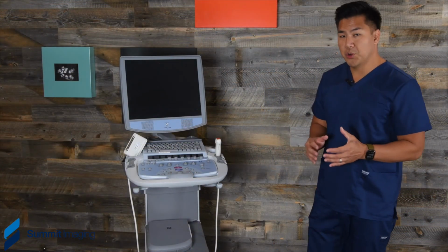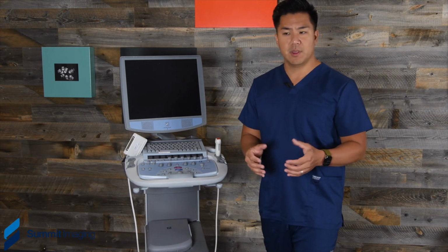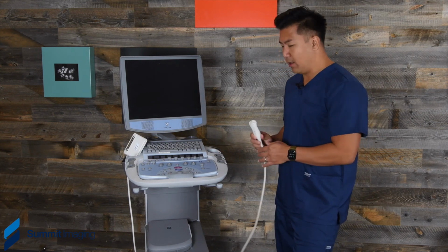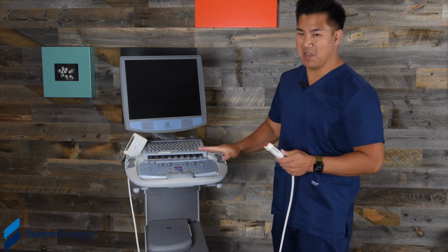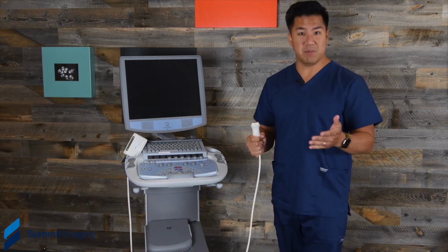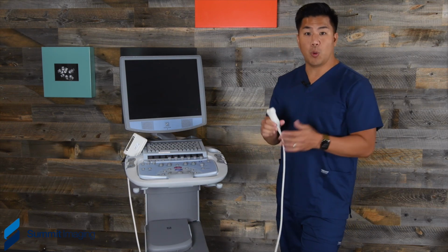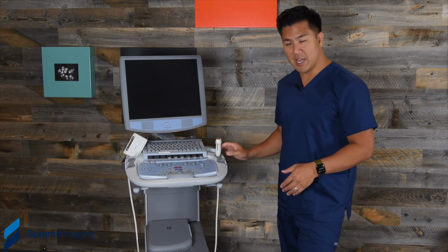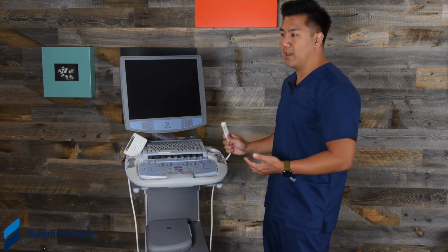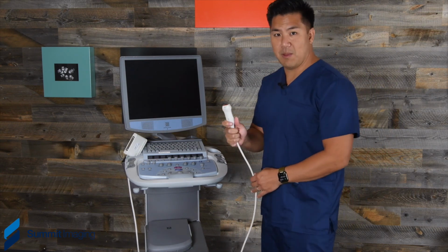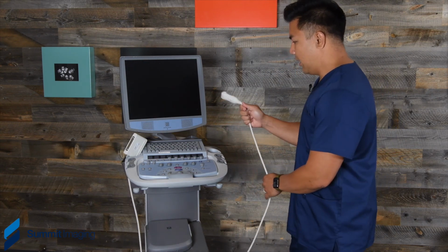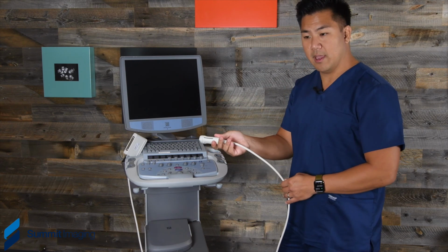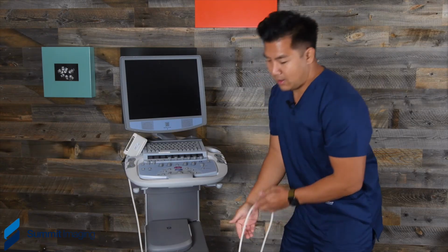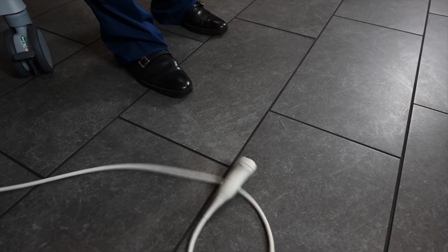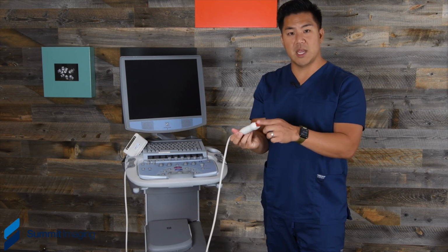All right, we wanted to show during clinical use some more standard probes that are more in a traditional ultrasound scanning room. We have our probe here for those that are scrutinizing the equipment. Yes, we know this probe does not work with this machine. This is purely for demonstrating the vulnerability during normal use of a transducer. And so oftentimes a sonographer will be working with a probe and hey, accidents happen. They'll be scanning, and then all of a sudden the probe may slip out of their hand and it will actually drop to the floor. That drop, this will naturally drop on its face, the most sensitive part of the crystal.